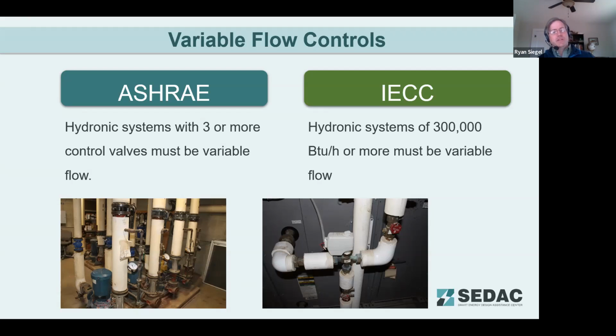So regardless of if that's several small systems or just a couple of large systems, a little bit different methodology here. Whereas ASHRAE is saying, hey, if you've got at least 3 zones, let's do variable flow for that, which is also being aided by that delta T of 15 degrees, really trying to lean on that and get better performance over the whole system.